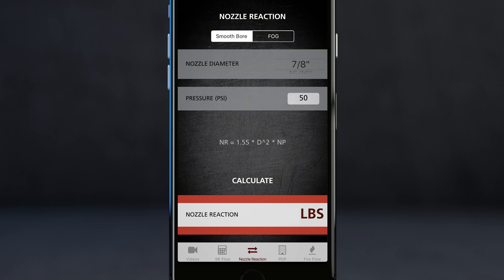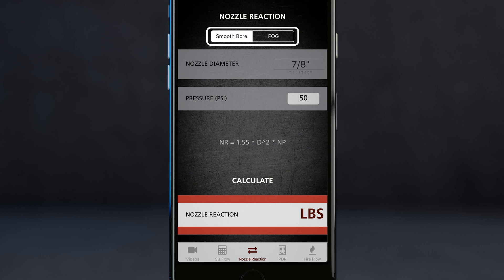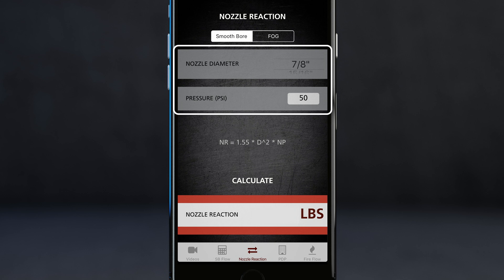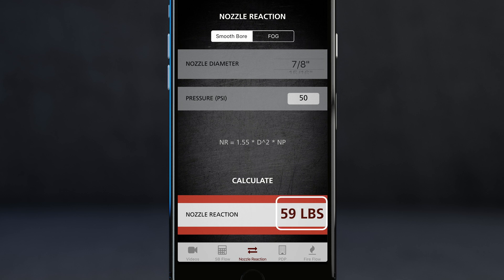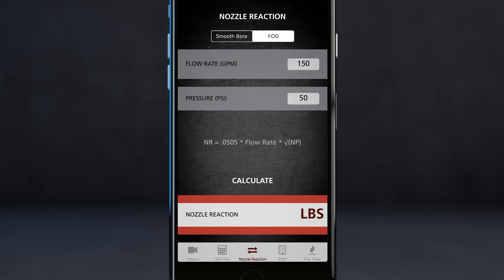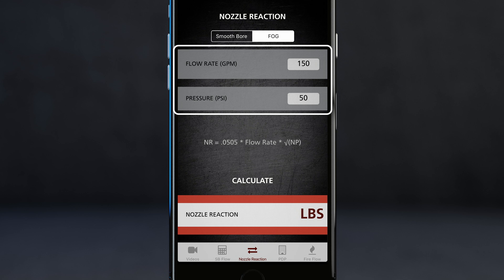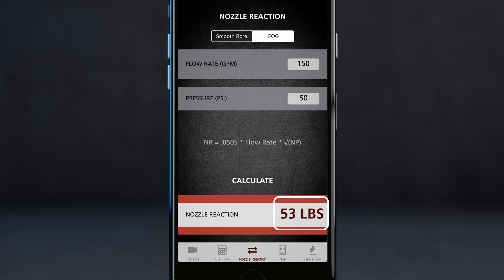The next section is a very convenient nozzle reaction calculator. This can be used for smoothbore or fog type nozzles. For a 7/8 smoothbore at 50 psi, I tap calculate and I have 59 pounds force nozzle reaction. If I tap over to fog, it defaults to 150 GPM at 50 psi. When I hit calculate, that shows me 53 pounds force nozzle reaction.